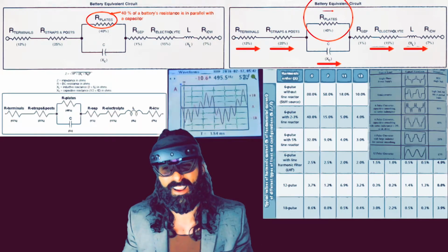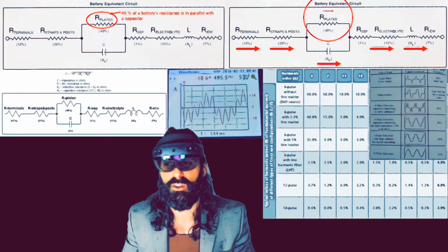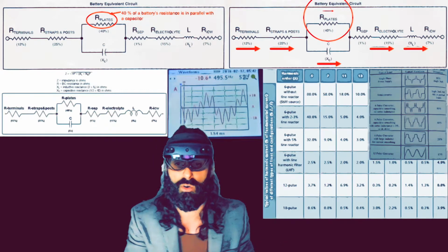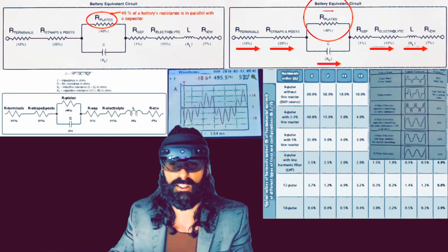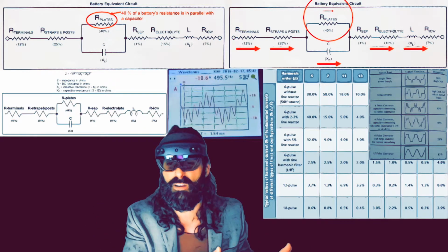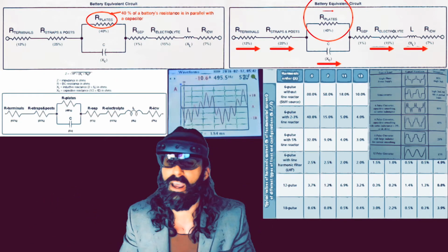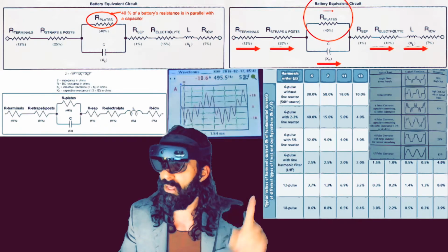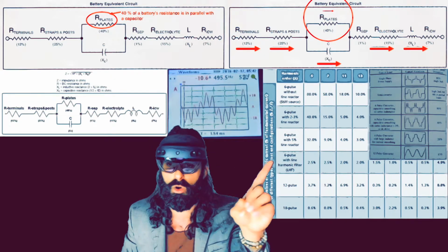And this is where I come back to the analog to digital converter resolution, the total number of bits. It's directly applicable to this as well. So monitors might work perfectly in a factory where there's no noise. Everything is essentially designed to operate at 100% efficiency. But when it gets out into the field, you have all of these other components that can drastically impact and affect the battery monitoring system. So again, coming back to this noise, AC impedance in this kind of environment does not work at all.